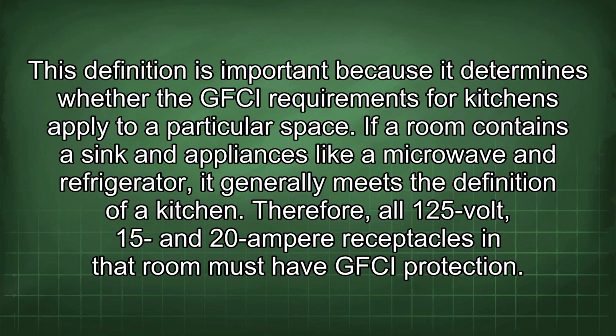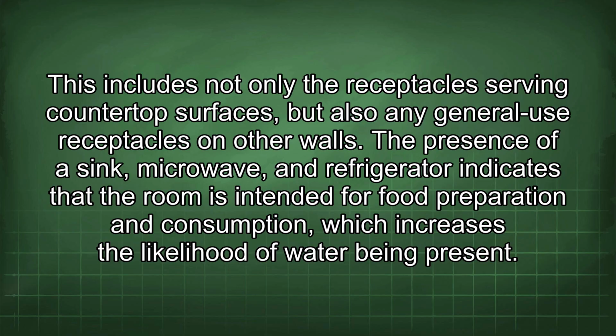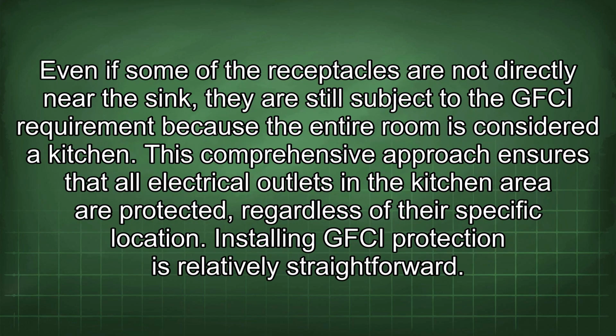If a room contains a sink and appliances like a microwave and refrigerator, it generally meets the definition of a kitchen. Therefore, all 125-volt, 15 and 20 ampere receptacles in that room must have GFCI protection. This includes not only the receptacles serving countertop surfaces, but also any general use receptacles on other walls. The presence of a sink, microwave, and refrigerator indicates that the room is intended for food preparation and consumption, which increases the likelihood of water being present. Even if some of the receptacles are not directly near the sink, they are still subject to the GFCI requirement because the entire room is considered a kitchen. This comprehensive approach ensures that all electrical outlets in the kitchen area are protected, regardless of their specific location.